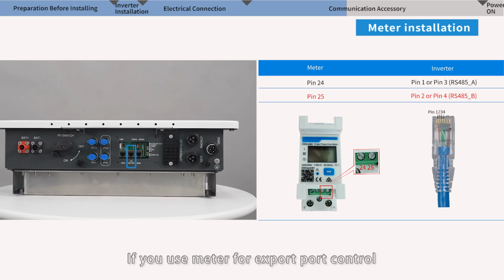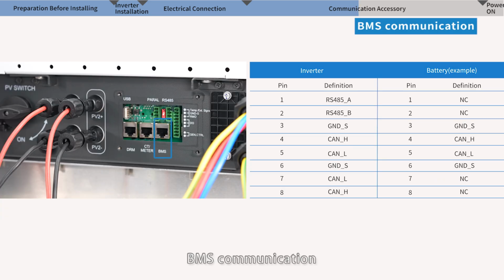Meter installation. If you use a meter for export port control, here please use pin 1 and 2 as A and B of RS485 communication with the meter. BMS communication.